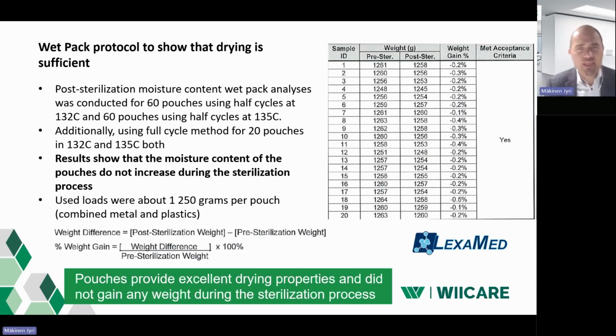Another interesting thing is the wet pack protocol. Lexamed also completed this. This is to show that the drying properties of these pouches are sufficient. So they were packing even 1.2 or more than 1.2 kilos in each pack, different metals and plastics, and then sterilizing them in different cycles. Before sterilization, they measure the weight of these pouches, and then after the sterilization, the weight of these pouches. The idea is, of course, that they are not gaining any weight during the sterilization process, so they would not be left wet after the sterilization. And the results showed that the moisture content of the pouches does not increase during the sterilization process.